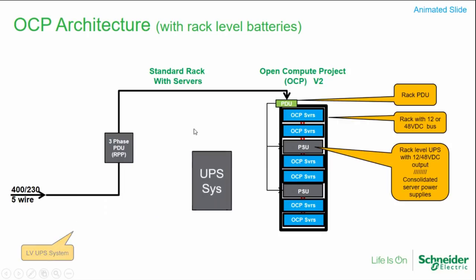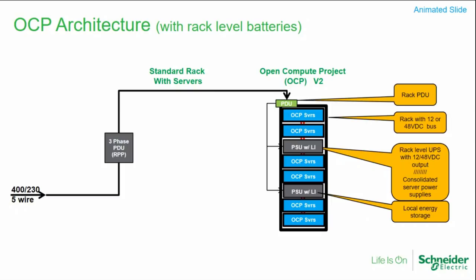Another interesting thing in the spec is that because of the advent of lithium-ion batteries — which are smaller, lighter, and allow more power in a smaller place — if you couple those power supplies with batteries, you can now put the UPS function right there in the rack. These are specified with maybe 90 seconds or maybe three minutes of runtime right there in the rack.